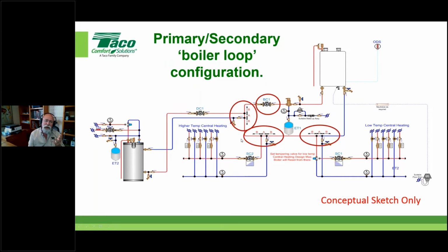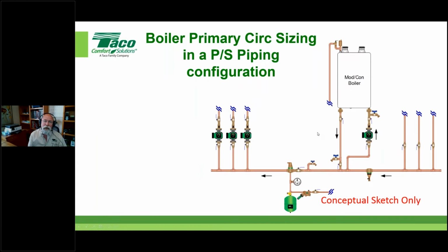Very cool. So I'm not going to elaborate on this. I will say that we're still talking about boiler circulator sizing, right? We're still talking about closely spaced tees, and all that applies. Okay. Here's what we typically see nowadays. Most of the boiler manuals out there, they're showing, for instance, this is depicting a wall hung condensing boiler. This is kind of how they show it. We have the near boiler piping, which is just relatively short. It just comes down and goes into the secondary portion of the system, right? So again, we're going to focus on these two things here. We're going to highlight this.